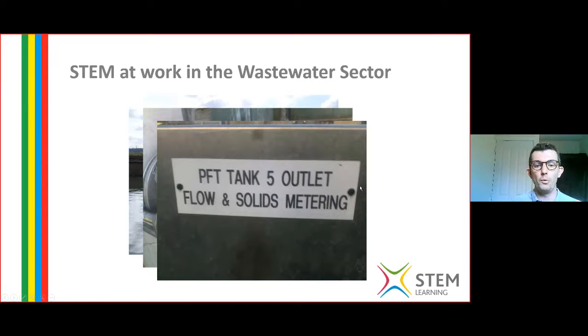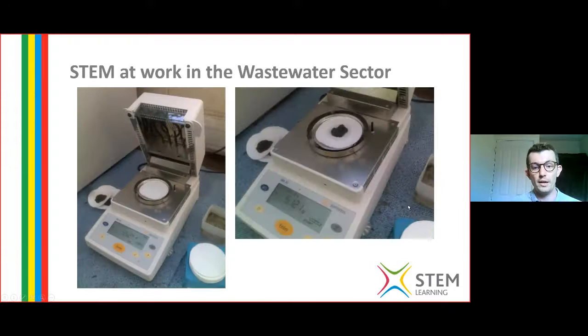To do this, we need to take a wet sample of the thickened sludge and then dry it in an infrared moisture analyzer, which weighs the sample once dry to provide a total dry solids percentage. This percentage is used in a factor calculation to calculate a new calibration factor to be keyed into the instrument transmitter.